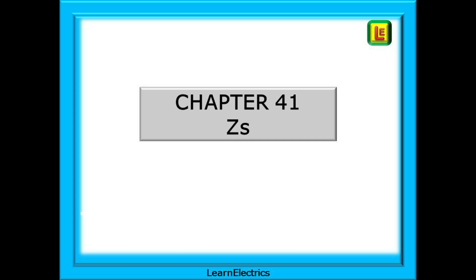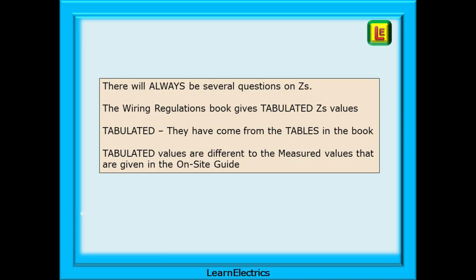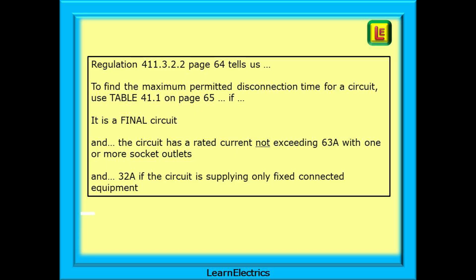Staying with Chapter 41, another big section for exam questions is ZS. Knowing what the maximum permitted ZS is for different circuits and different fuses or breakers is so very fundamental to our trade, and this is reflected by having four or five questions in the exam just on ZS. There will always be several questions on ZS in every exam and you need to know how to answer them. The wiring regulations book gives tabulated ZS values — tabulated means they have come from the tables in the brown book. Tabulated values are different to the measured values given in the amendment to wiring regulations book.